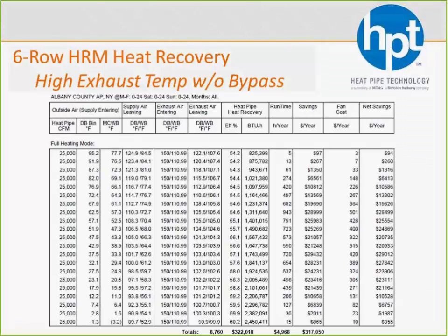Let's say it's not comfort heating. Let's say it's process heat, and therefore even on a hot day of 95 degrees, we still want to take that heat and heat it up. That's going to still be exhausted at 150 degrees. Well, now we're taking every bin of the year and taking as much heat as we can all the time, not bypassing anything. Now instead of $26,000 in savings, you've got over $300,000 in savings. Now we're not talking years of payback. We're talking days or weeks.